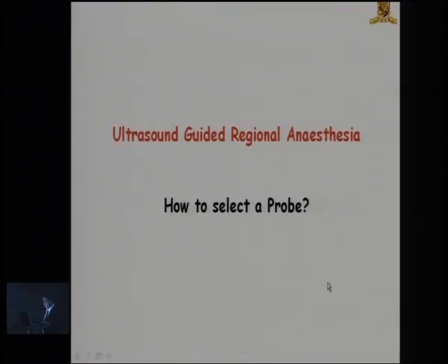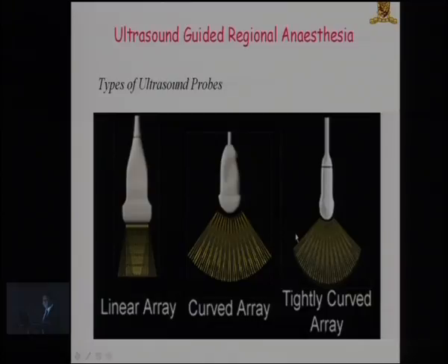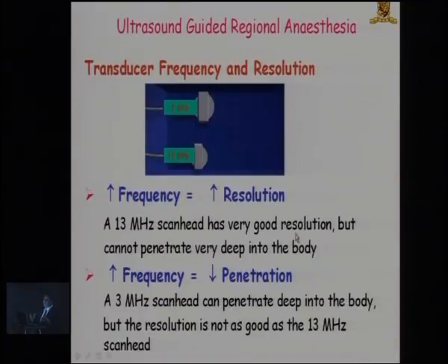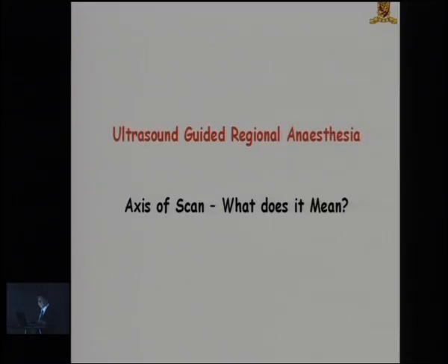So how to select a probe? Again, this has been discussed previously, the different kinds of probe, linear array, curved array. Now, depending on what you are trying to scan, if you're looking at a superficial structure, by now you should know that you want a high frequency probe. A high frequency probe will give you better resolution, but the depth of scanning will be much more superficial. Whereas if you're looking at a deep structure, you need a low frequency probe, but at the same time, because it's a low frequency probe, your resolution is not that clear. So this will determine what probe you need to choose for your scan.